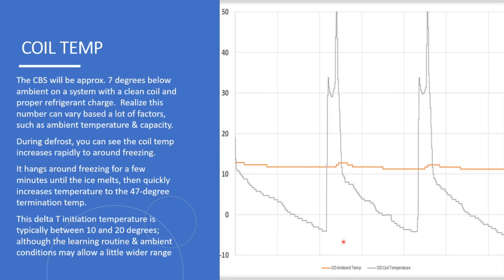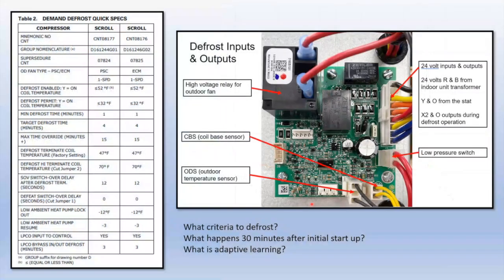So both sensors are important because there's going to be a delta between the two. So we have our defrost board, and this is the basic layout of it. We have a relay here that the outdoor condenser fan goes through. This can cut the condenser fan during a defrost, which we'll get into. We have our 24-volt wiring harness with your R, common, Y, O, and X2. We have our low pressure switch that plugs into the board.